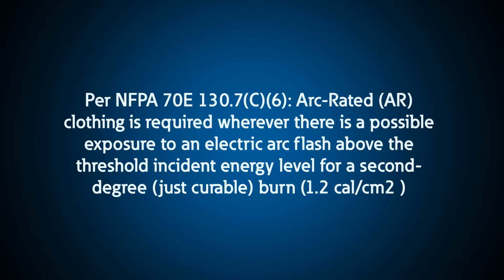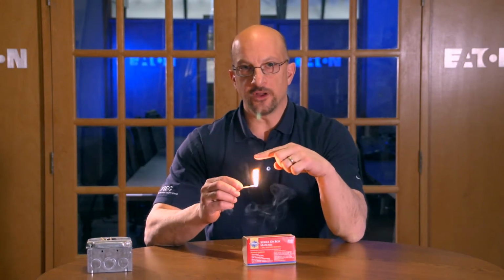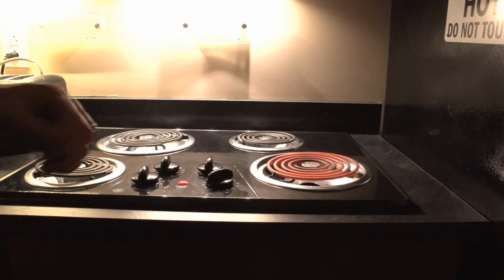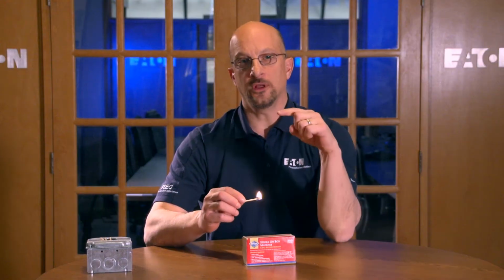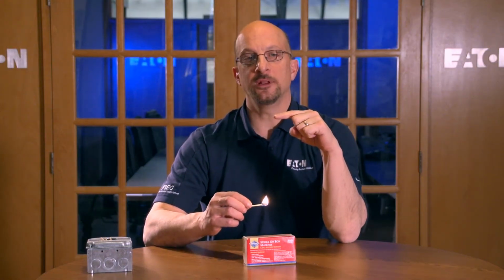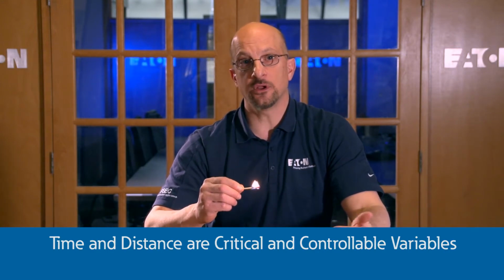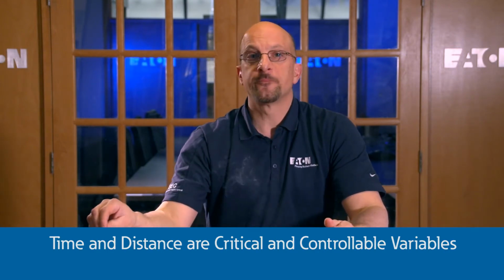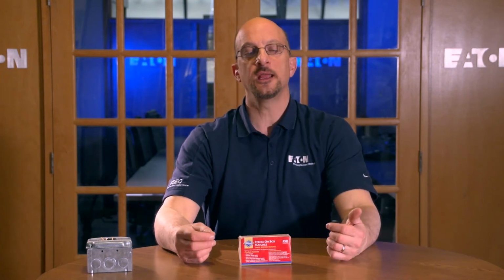As you can imagine, if you pulled your finger away quickly, as you would do when you touched a hot stove, or if you held the match 10 inches away, there would be less heat. This illustrates that time and distance are critical and somewhat controllable variables. Similar to an arc flash event, if we can control the time and distance of the arc flash, we can lessen the impact. Here at the Experience Center, we can show you options that reduce the time of the arc flash event and increase the distance of the worker to the location where the arc flash occurs.